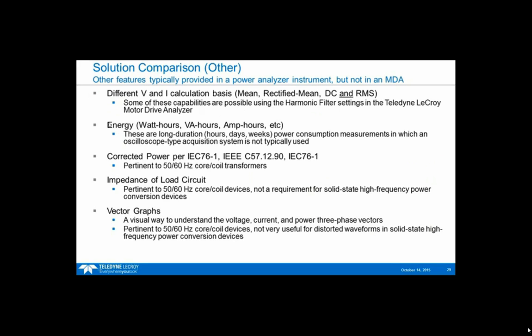Power analyzers, generally, they're not acquiring data. So since they're not acquiring data and storing it, they can process on the fly. And so they're very optimized for looking at very long durations and measuring energy consumption, which would be great for something like a refrigerator, for Energy Star measurements or something like that. Those are not typical applications for a motor drive analyzer, but is a typical application for a power analyzer.